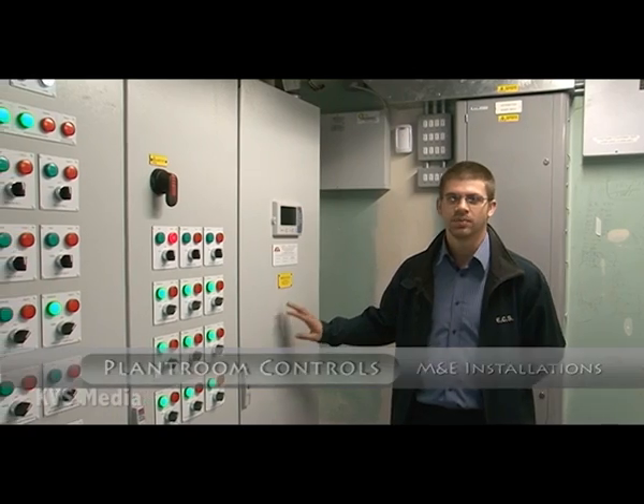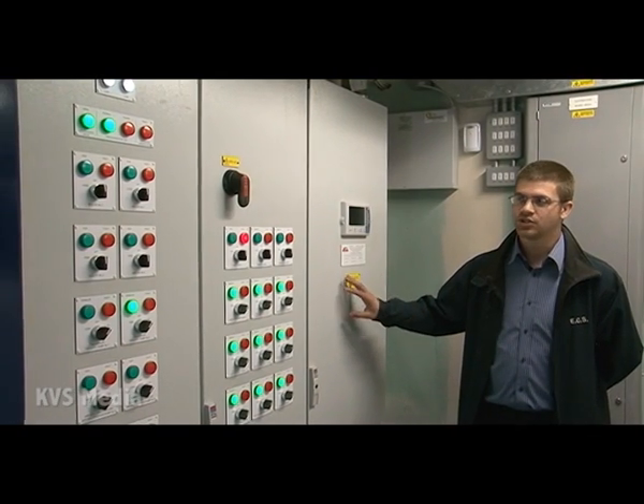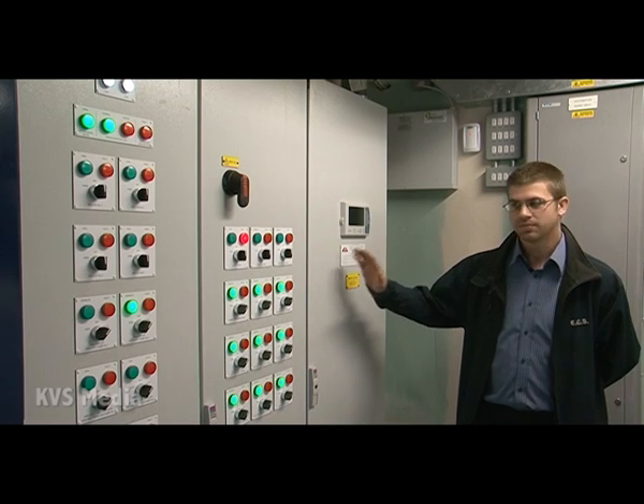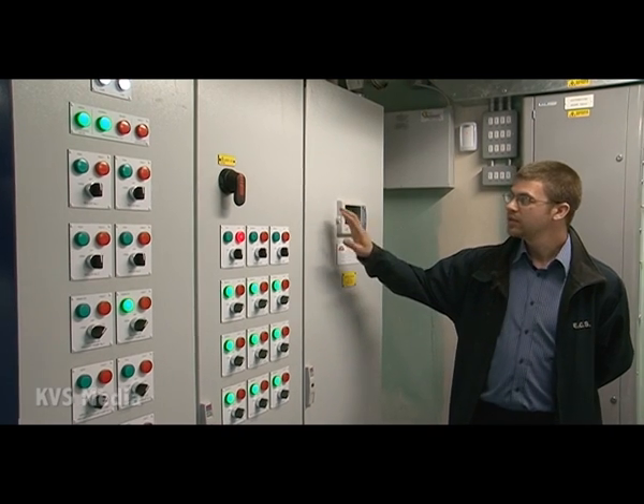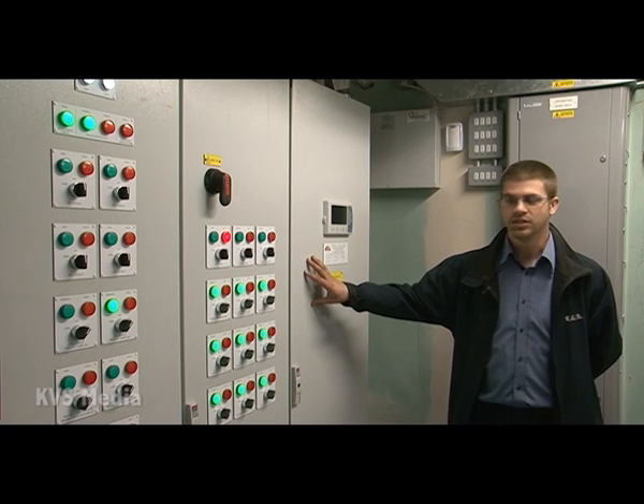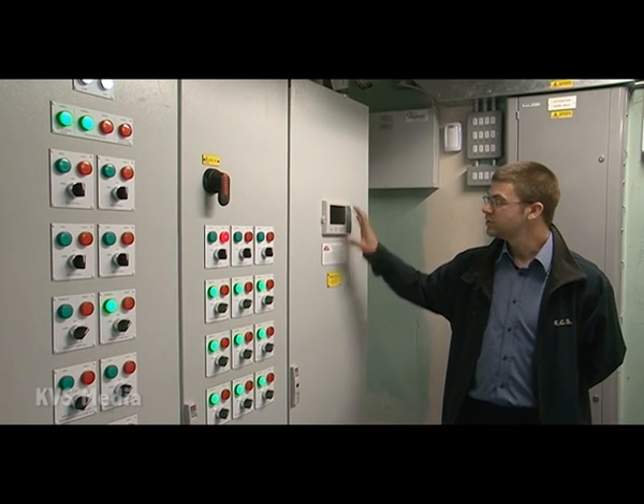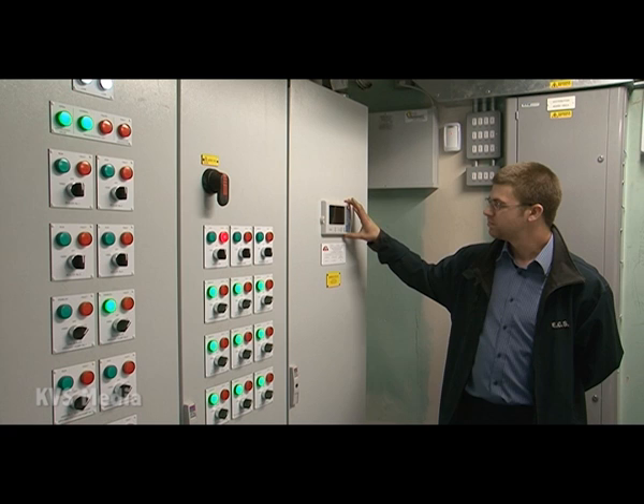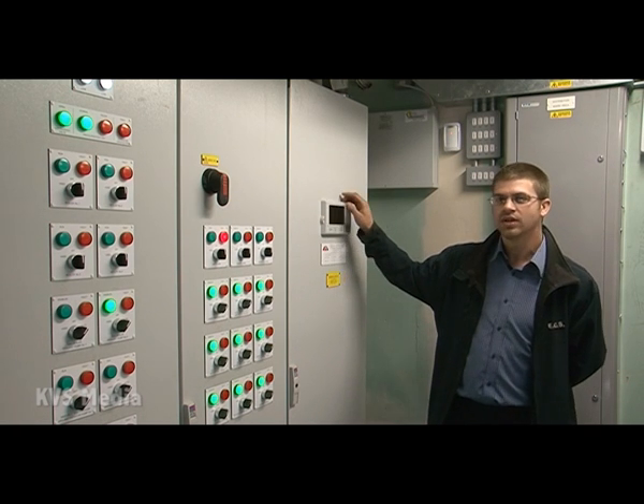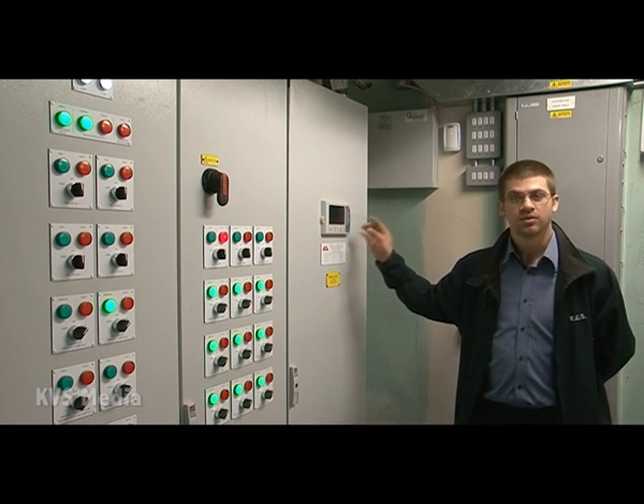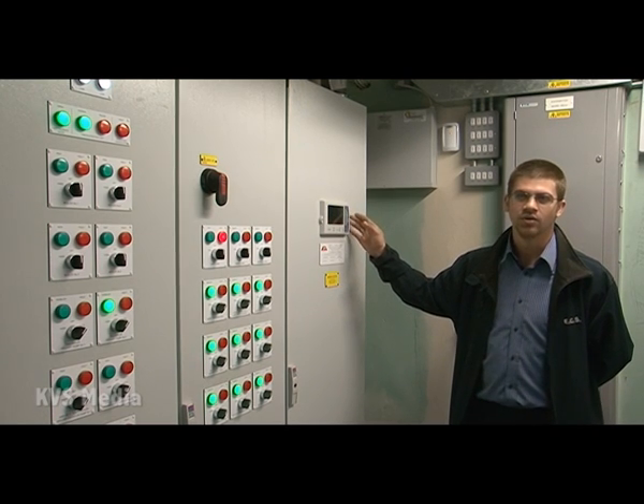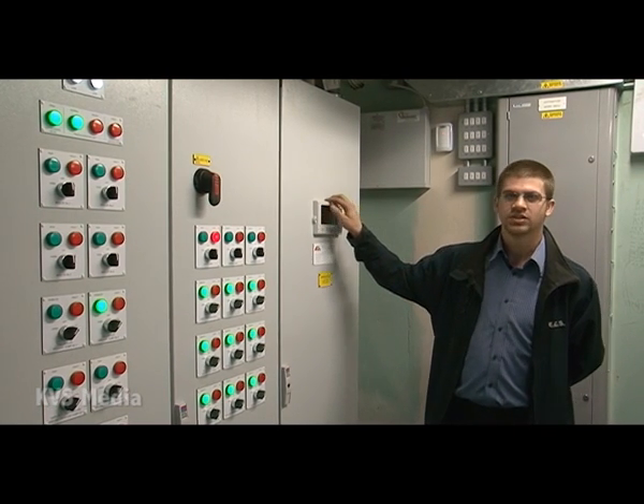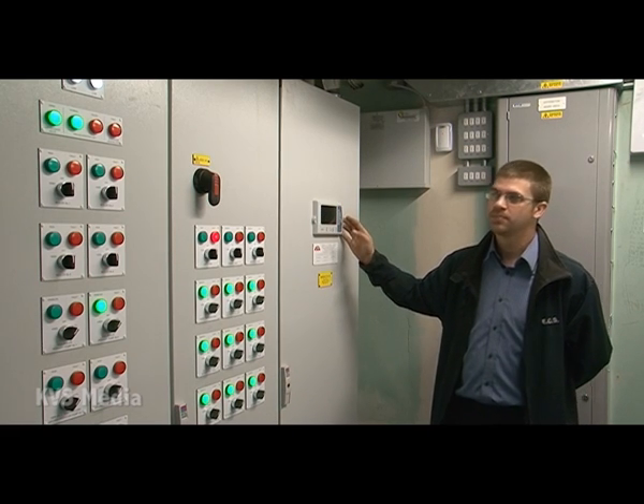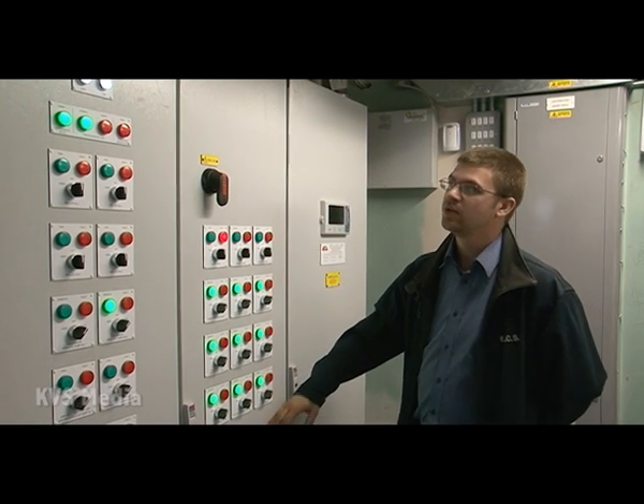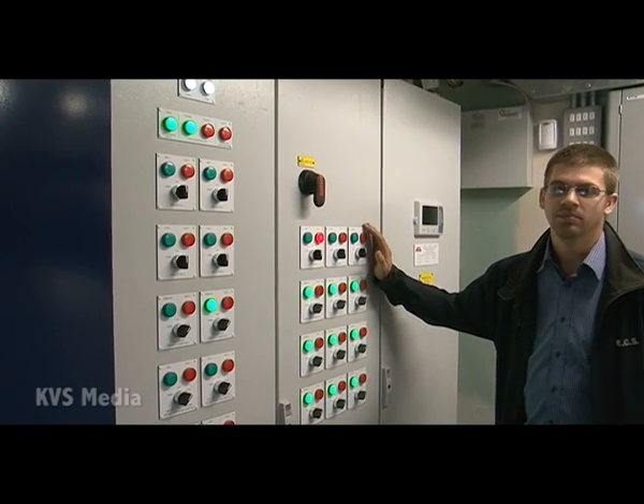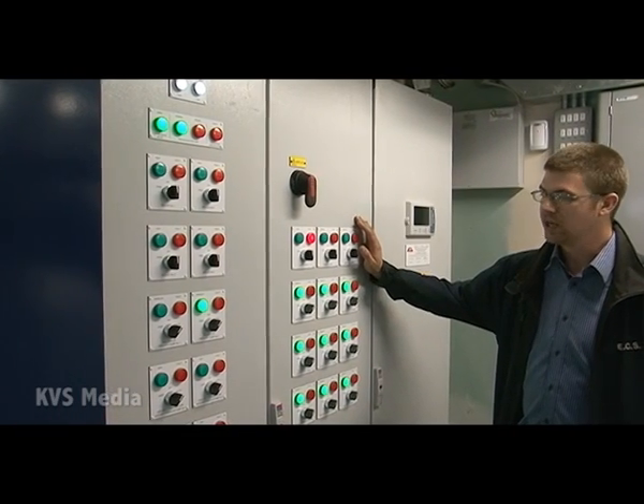This is the main control panel. There's a number of these dotted around the school. This is, like I say, the main one. Within this compartment there's some low voltage BMS controllers. This is the BMS controller interface. It's more intended for use by engineers, although users can enter a basic mode and view various statuses and set points of the system. Within this section we've got all the mains equipment and the power and switch gear.